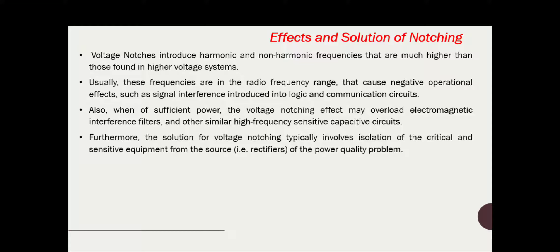What are the effects of notching? Voltage notches will introduce harmonic and non-harmonic frequencies that are much higher than those found in the higher voltage system. Usually these frequencies are in the radio frequency range, which can cause negative operational effects such as signal interference introduced into logic and communication circuits where radio frequency is a concern.